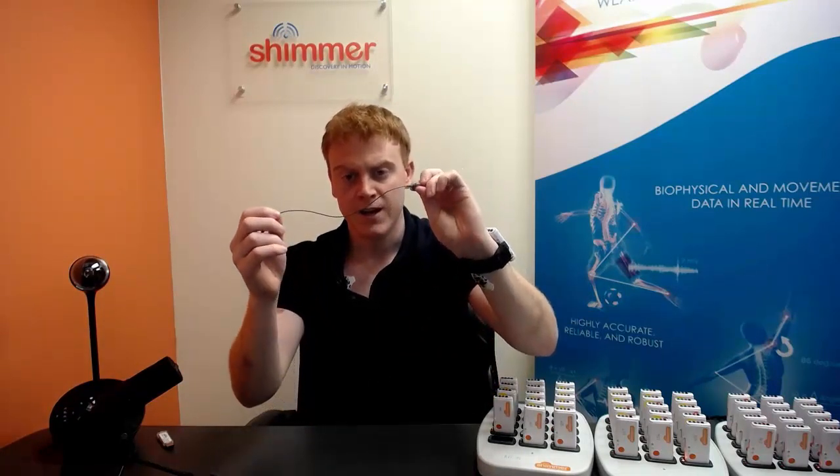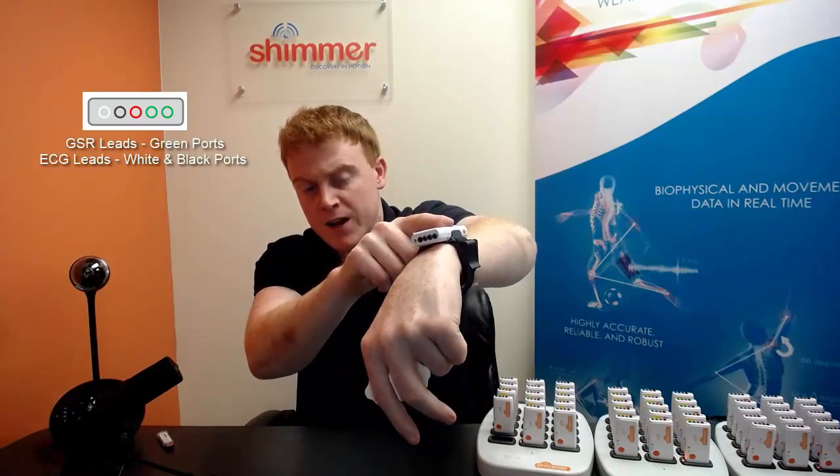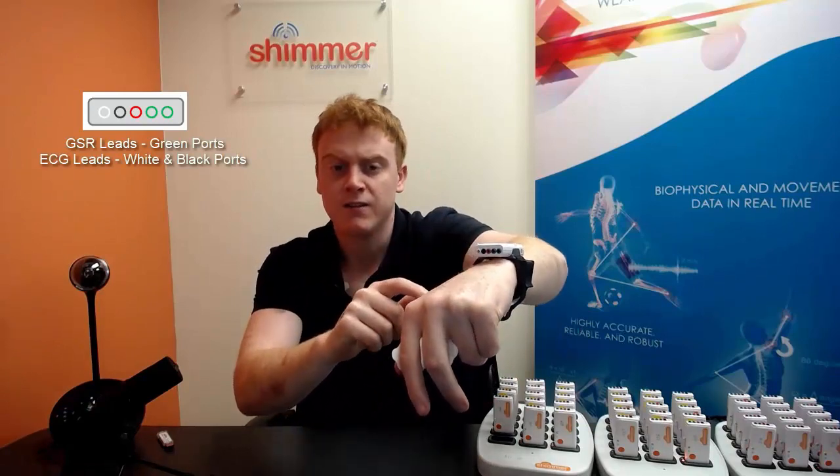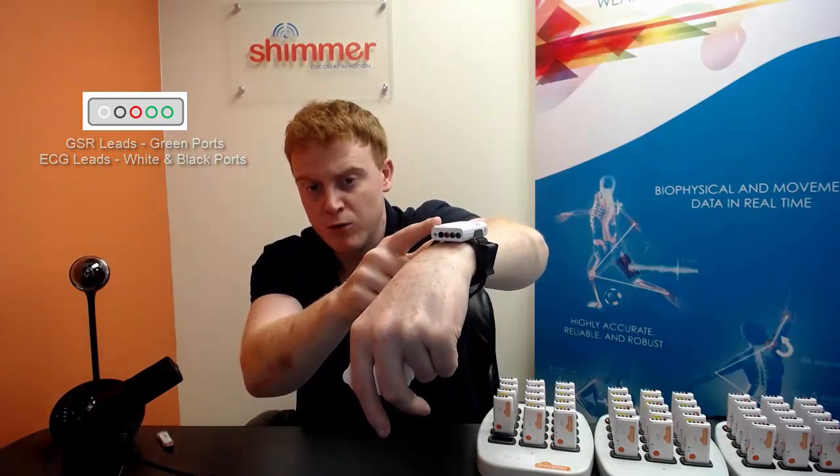Next I am going to snap the leads into the electrodes and connect the leads to the sensors. The leads connected to the GSR electrodes will go in the green ports on the sensor and the leads connected to the ECG electrodes will go in the white and black ports.